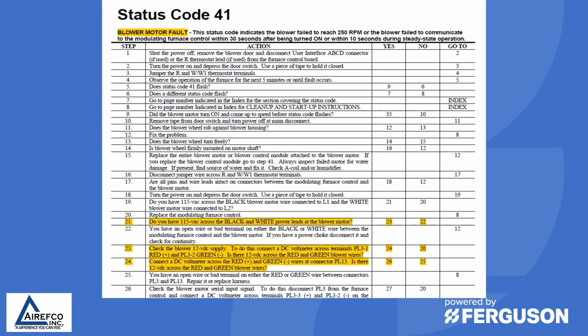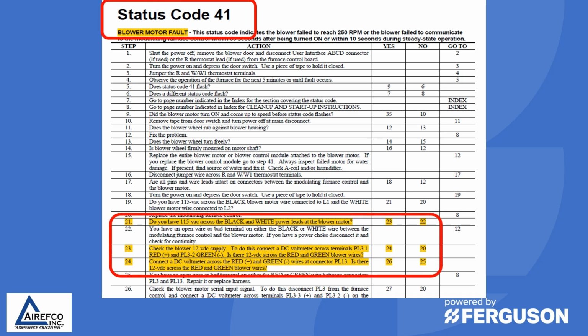On this page of the troubleshooting guide, we have status code 41, which is a blower motor fault. Whenever you're checking an ECM motor, you should of course first check that you have your line voltage, either 115 or 208, 230. ECM motors will be powered continuously by high voltage. Then it directs us to check the 12 volt DC supply between the red and the green terminals.